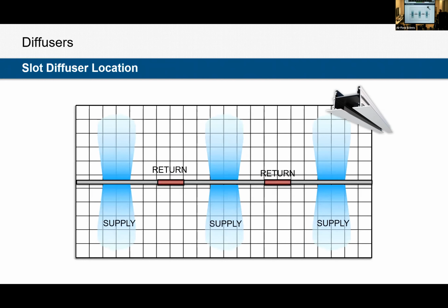Yes. A really good design, what we recommend, is putting them in line with the supply. You would have a supply section, maybe an inactive section and a return section. From the room side, it's a really nice, beautiful continuous slot that makes the occupant feel really nice, but above, we know that we've got some variability in the slots. If we're supplying out of one section, it has no choice but to make its way into the room to get pulled back up into the middle. So this is the best design for slot diffusers here. Whoever that was, they get 2 points.